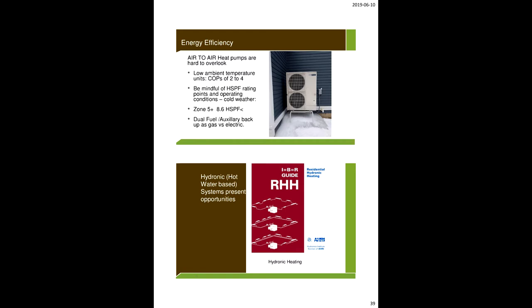I learned a bad lesson. Every Saturday I was out with a pneumatic hammer for the first 2 years, taking the ice out from underneath. You can do that, or you can put it on a slab in Alberta and you don't have a problem—it's minus 40 out there, they have no moisture, it doesn't condense enough. You put it here, I had 20 inches of ice underneath this. Again, it's a humidity levels issue.